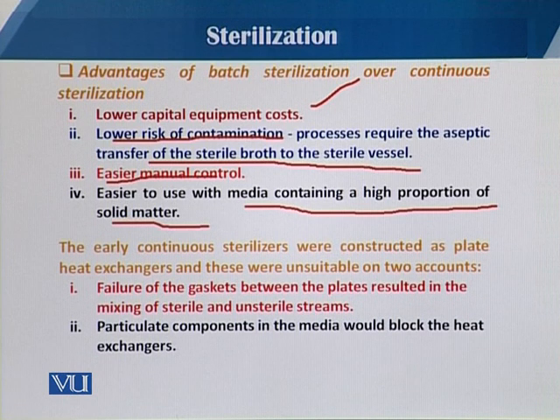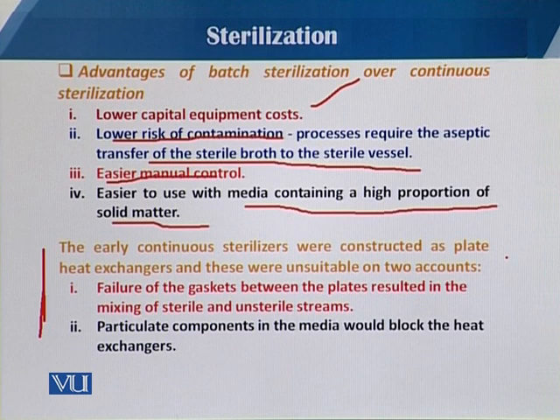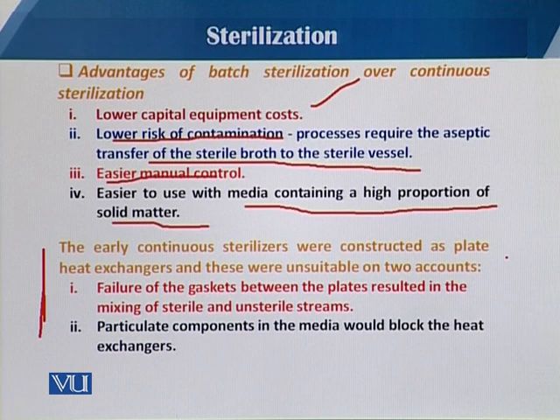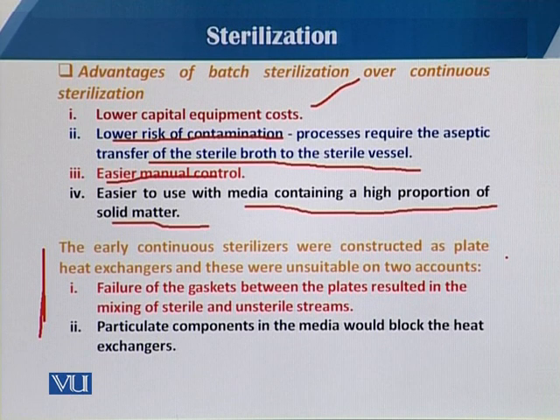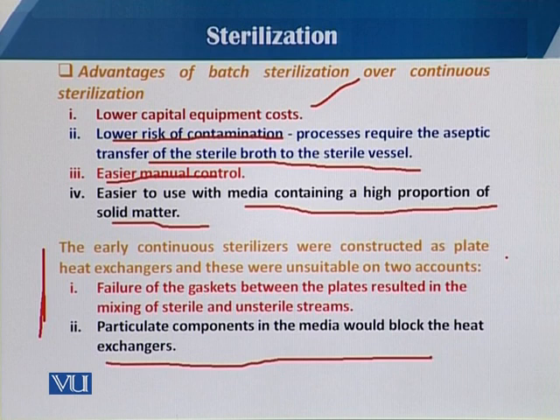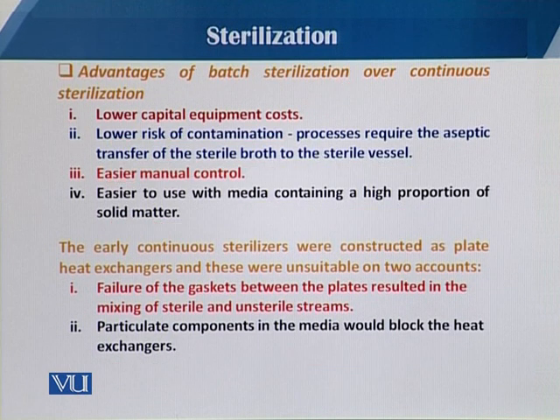Early continuous sterilizers were constructed as plate heat exchangers, but these were unsuitable for two reasons. First, failure of the gaskets between the plates resulted in mixing of sterile and unsterile streams. Second, particulate components in the medium would block the heat exchangers, because the passages are very small, and viscous media caused blockage leading to greater losses.